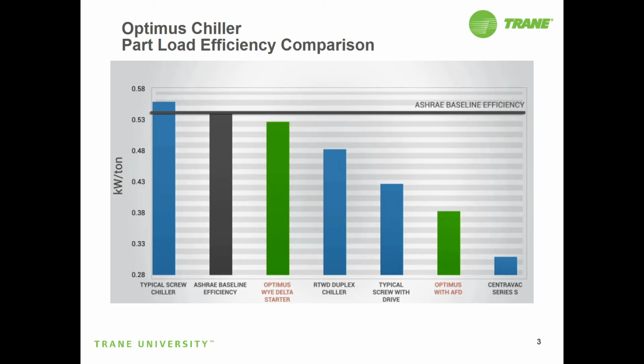However, it should be noted that there's also the benefit of the AFD being the best method of starting the motor. The AFD brings the motor up to speed in a controlled manner without the locked rotor current spikes as with motors that use contactors. The sales engineer should discuss with his or her customer the advantages and disadvantages of each starter and choose which is best for his customer's needs.